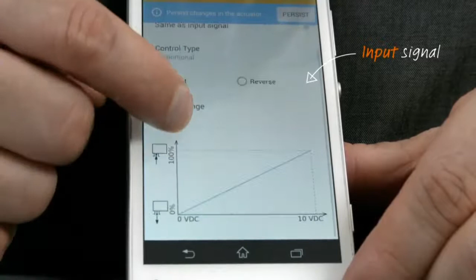I can choose the speed. I can set up the valve to which the actuator is connected, which allows me to adjust the stroke through a flow value. Through an extended menu, I get access to calibration parameters, characteristics that can be adjusted.